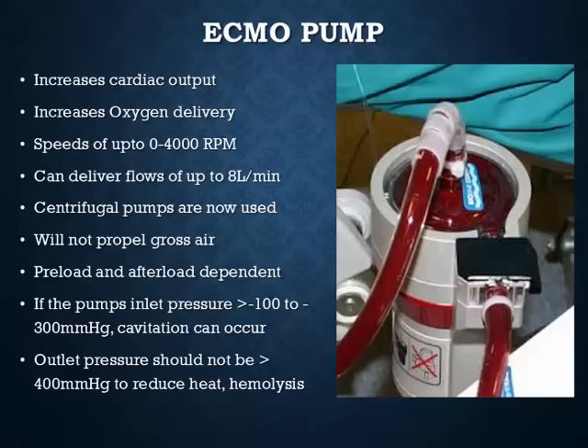The ECMO pump increases cardiac output and oxygen delivery. Speeds can go up to 4,000–5,000 RPM depending on the machine, and these machines can deliver flows up to 8 to 10 liters per minute. Centrifugal pumps are now most commonly used. They will not propel gross air into the patient, and they are preload and afterload dependent — they work on a servo mechanism. Inlet pressures shouldn't exceed negative 100 to negative 300 mmHg, otherwise cavitation can occur. Outlet pressures shouldn't exceed 400 mmHg, otherwise you can get heat development or hemolysis.